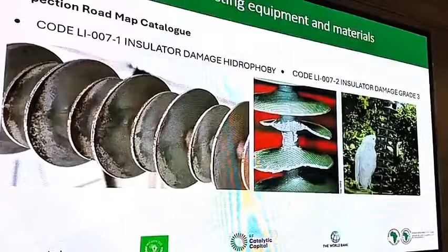During our survey of the entire LEC grid, we detected some violations and bad practices in equipment use. We saw bypassed fuse lockouts, which is very dangerous, poor earthing arrangements, misused joints, and transformers leaking oil. We also saw a lack of physical protection around transformers and other high voltage equipment, which would be critical if someone touched it.